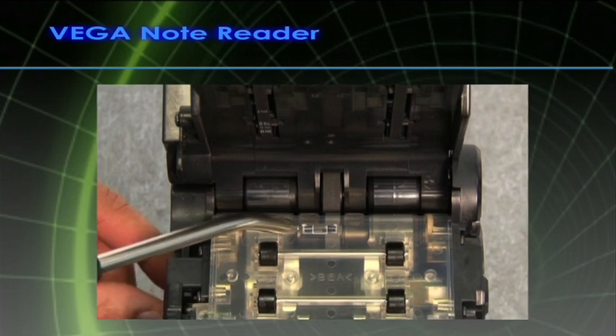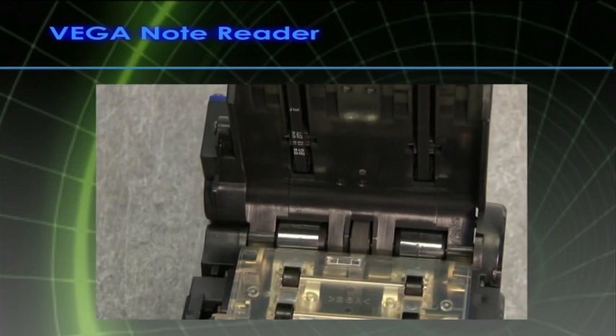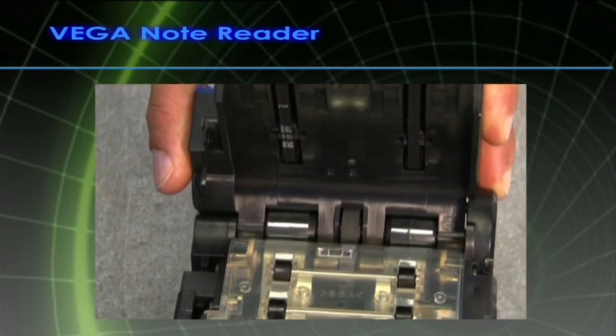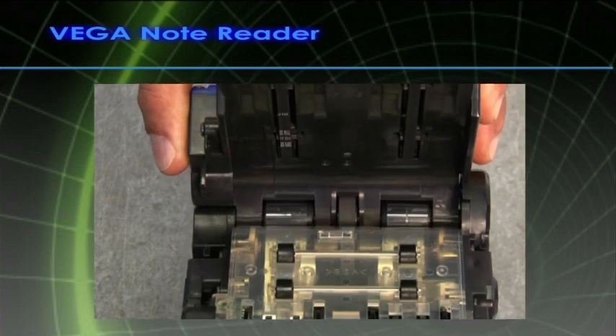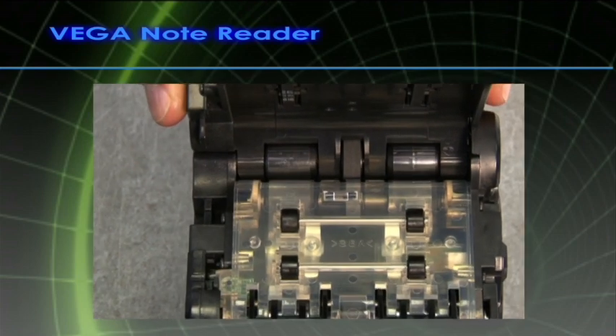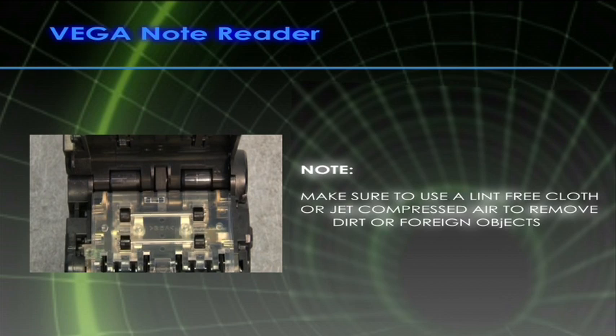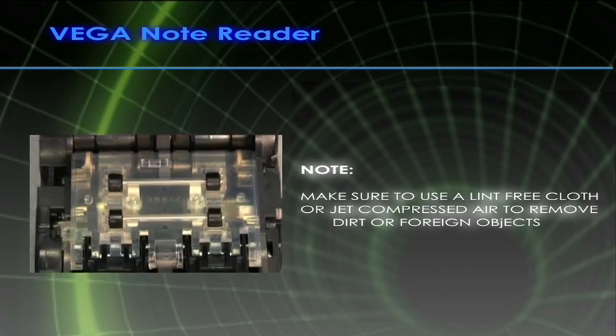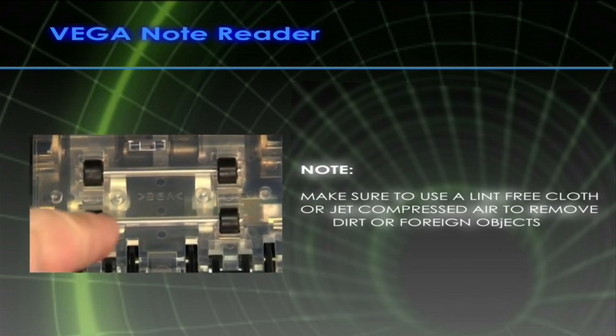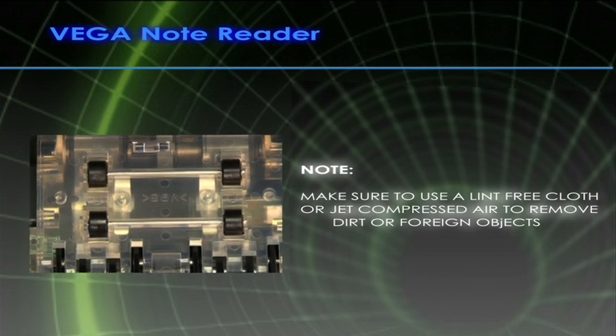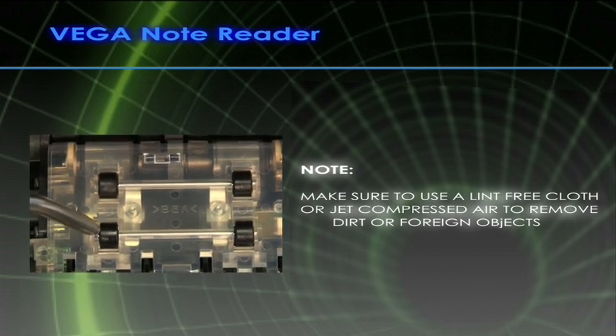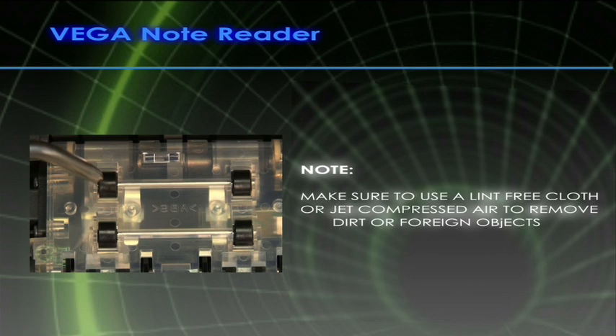foreign objects. Open the rear cover and clean the exposed rubber rollers and the 4 optical sensors. Clean the pinch roller and the 4 prisms. Make sure to use a lint-free cloth or a jet of compressed air to remove dirt and foreign objects. Use a pressurized air jet to blow out collected stubborn dust and debris from the unit.